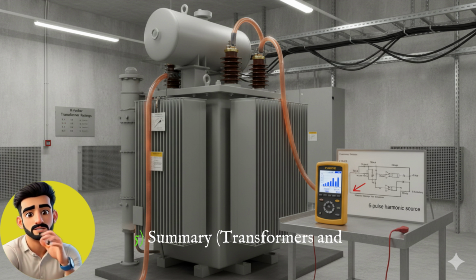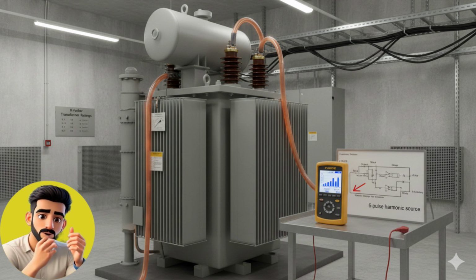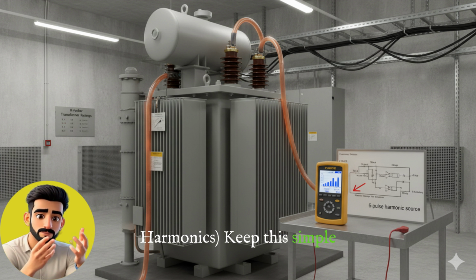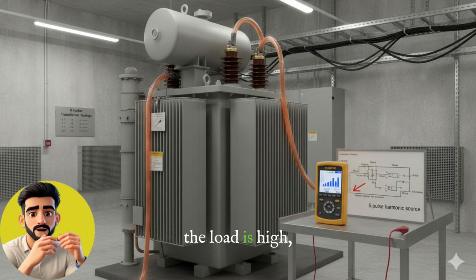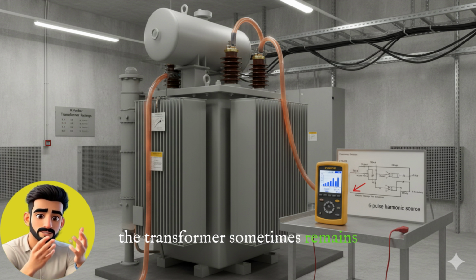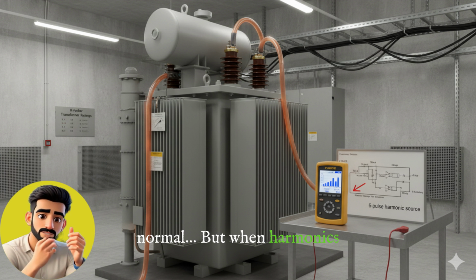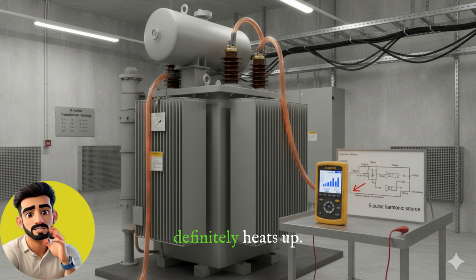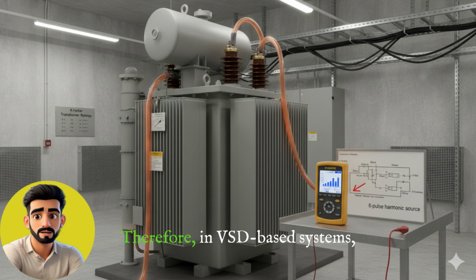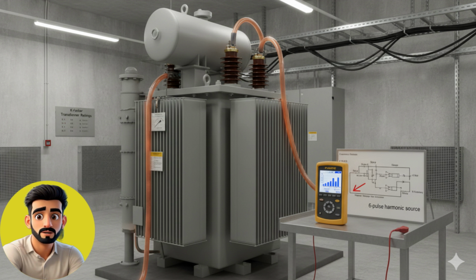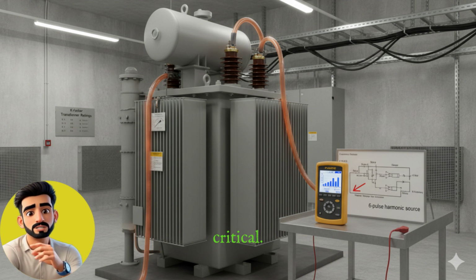5. Summary: transformers and harmonics. Keep this simple point in mind. When the load is high, the transformer sometimes remains normal. But when harmonics are high, the transformer definitely heats up. Therefore, in VSD-based systems, transformer rating, K-factor, and harmonic mitigation are very critical.